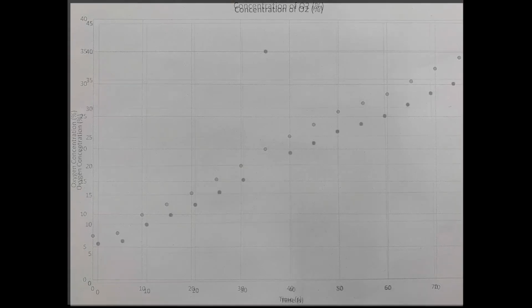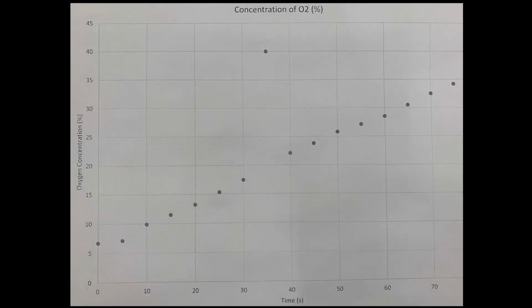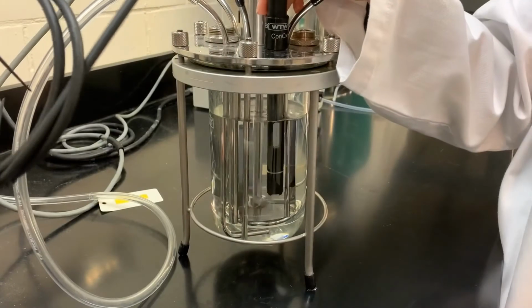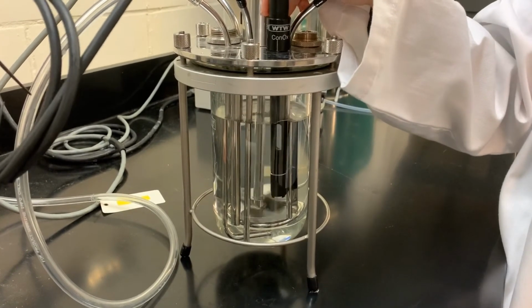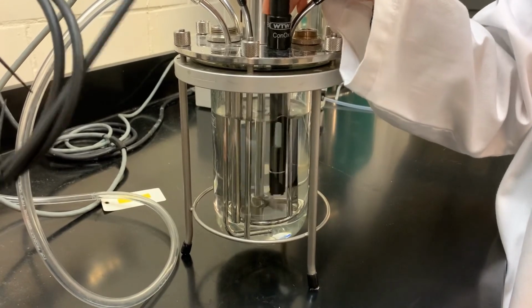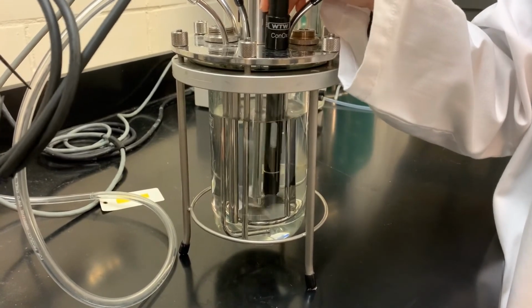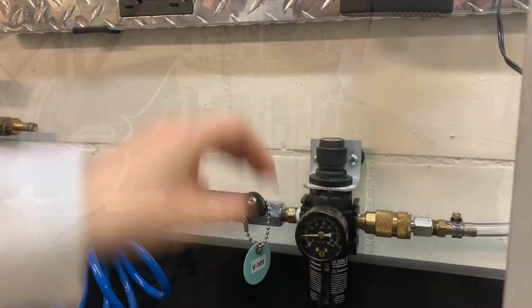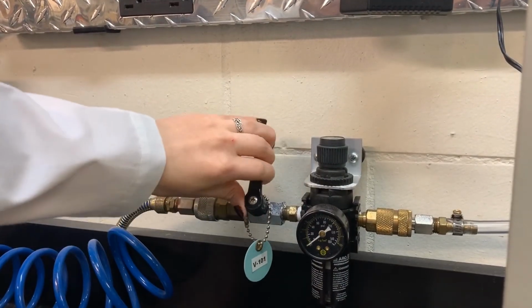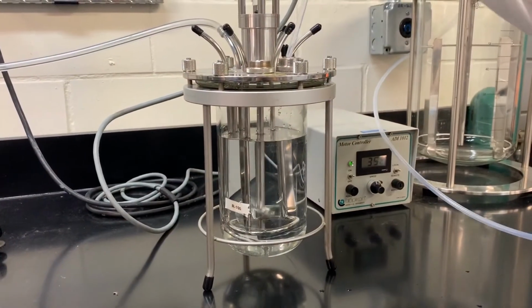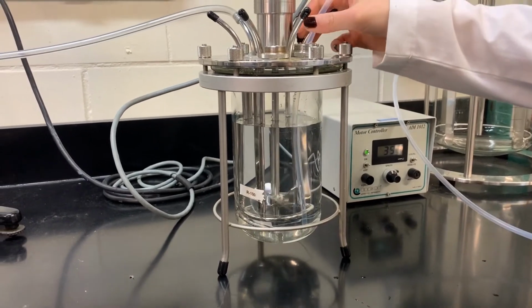If there is a large increase in the concentration of oxygen on the DO probe, it is likely the result of a bubble hitting the surface of the DO probe. If this occurs, the trial must be redone. In order to mitigate this issue, slowly swirl the DO probe in the bioreactor to ensure bubbles are not caught on the surface of the probe. Upon the completion of the trial, close valve V101 and begin the sparging procedure once again until the oxygen percentage returns to about 0.